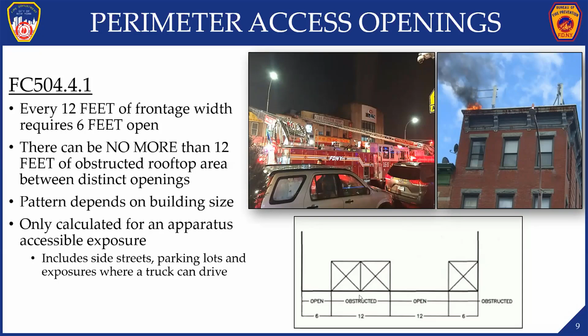Perimeter access openings need to be a minimum of 6 feet in each direction - 6 feet wide, 6 feet deep. They must connect to a clear path. Fences shall not obstruct the perimeter access landing, meaning you cannot have a fence within those 6 feet, because how is the firefighter going to land? They're not going to land onto that fence. You can't have fences between the clear path and the perimeter access opening.